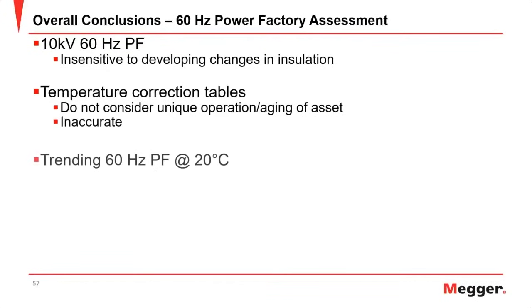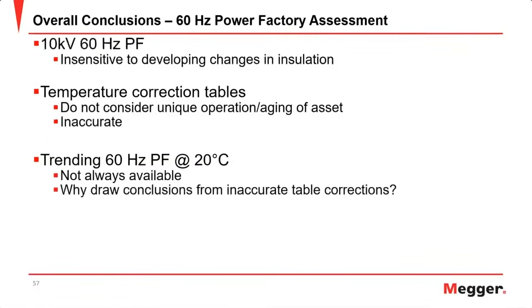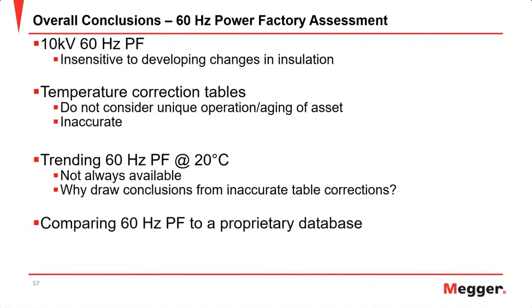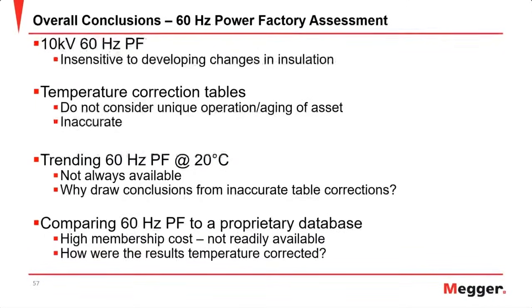And then trending at 60 hertz might not always be available. And then again, why would you want to draw conclusions from these results that were corrected to 20 degrees C, potentially using these incorrect temperature correction tables? Then lastly, you do have the option of comparing your 60 hertz values to a proprietary database. Typically, these do come with a high membership cost, but then you also have to question how these results were temperature corrected. If the results in this proprietary database did not take into account the unique aging of that insulation system, then they may not apply to that particular bushing that you're trying to evaluate.